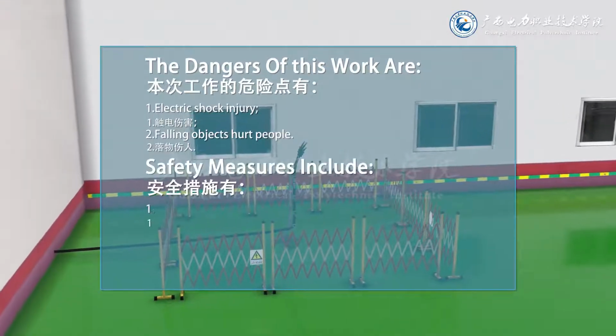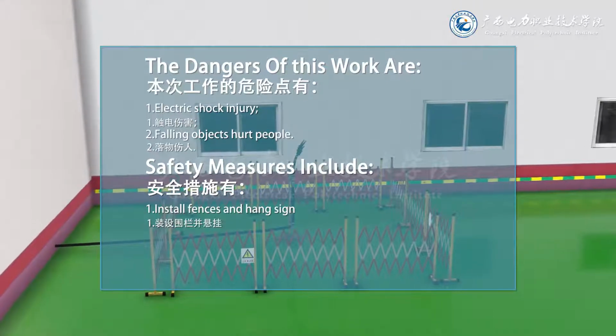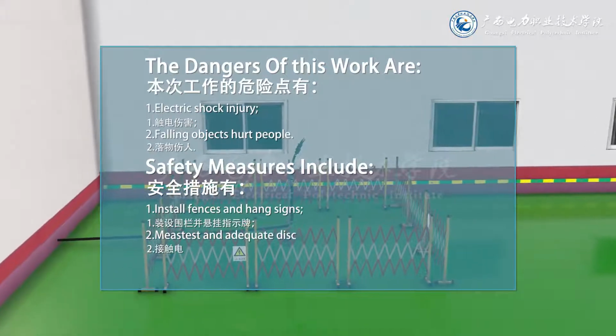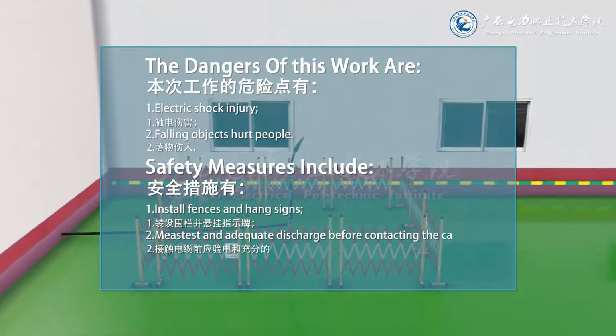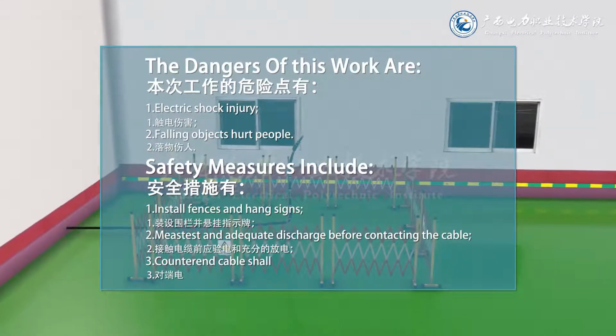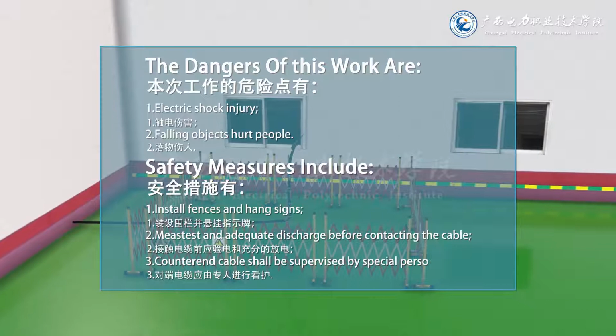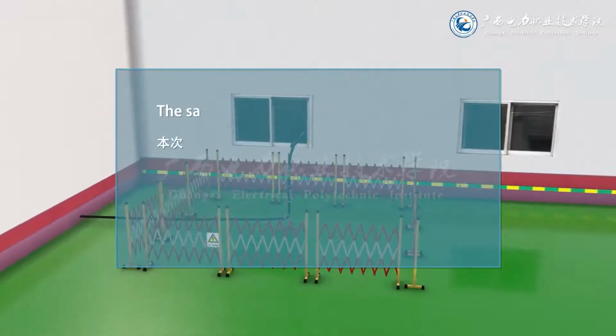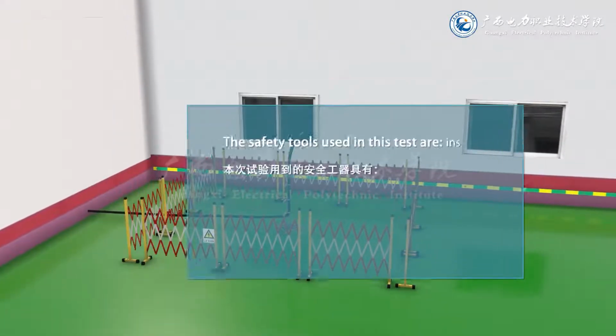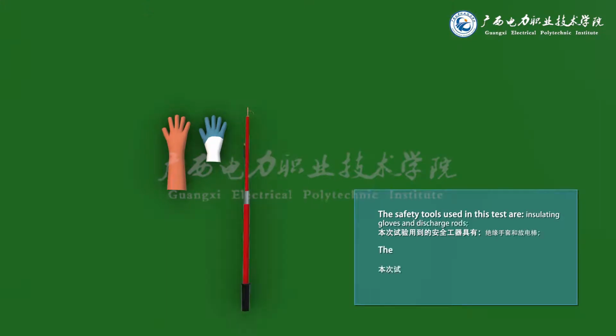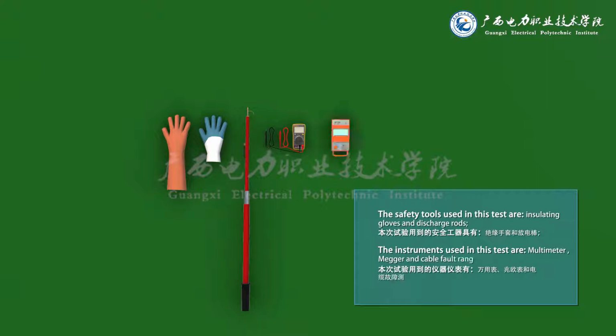Safety measures include: 1. Install fences and hang signs. 2. Test with a multimeter and fully discharge before contacting the cable. 3. The opposite-end cable shall be supervised by special personnel. The safety tools used in this test are insulating gloves and a discharge rod. The instruments used are a multimeter, a megohmmeter and a cable fault rangefinder.